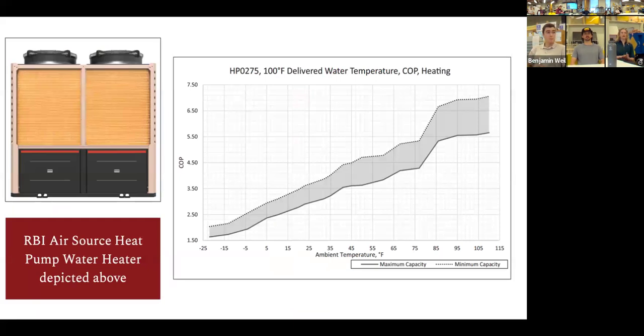As you can see here, this is a graph of the coefficient of performance of the heat pump in heating mode. And as the outdoor temperature increases, the coefficient of performance increases as well, as it's easier to heat the air. And we're using an RBI air source as the design for that.